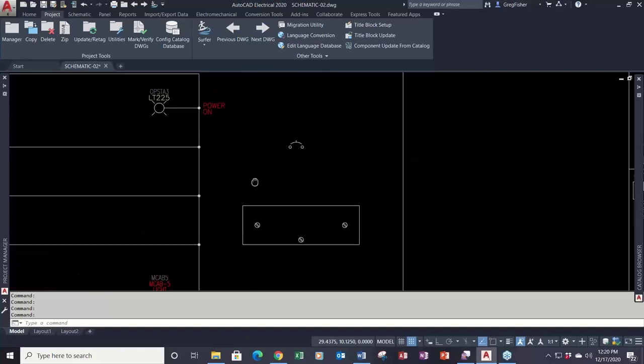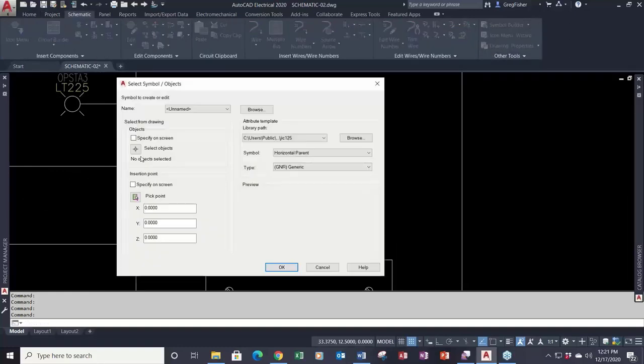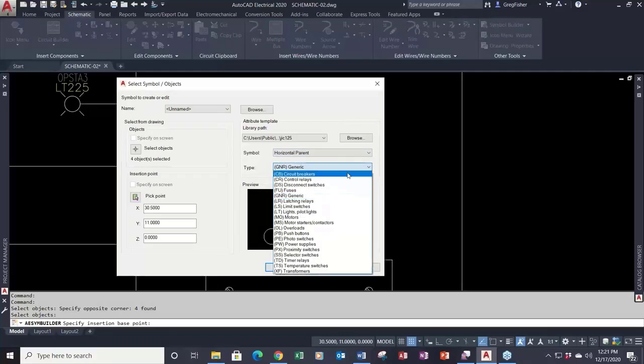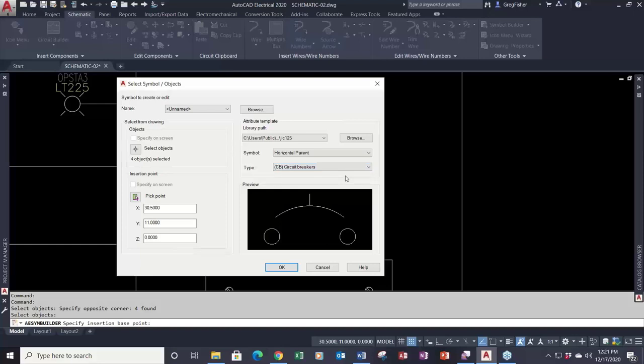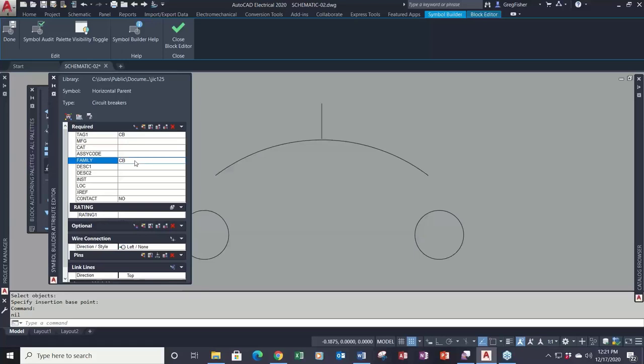Now I'm going to actually create the circuit breaker symbol. I'll go back to the symbol builder, select objects, pick a base point. It's going to be a horizontal parent, and I have the CB category right there under type. I'll click OK. Notice the family code — when I chose generic both fields were blank, but when I choose CB it automatically plugs in both the family code and the tag. I can change the tag if I want, but I'll leave it the same.